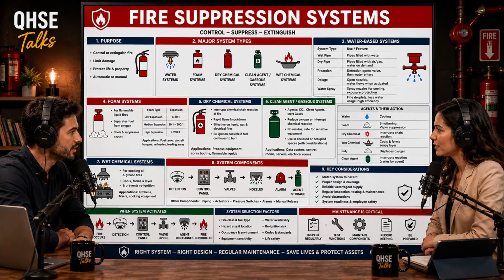Halons were considered the absolute wonder drug of fire suppression for the latter half of the 20th century. What made them so magical? They attack that elusive fourth leg of the fire tetrahedron. When halon gas hits the heat of a fire, it releases bromine or chlorine atoms. These atoms aggressively seek out and bond with those highly reactive hydroxyl radicals we talked about earlier. They chemically interrupt the chain reaction, killing the fire almost instantly.